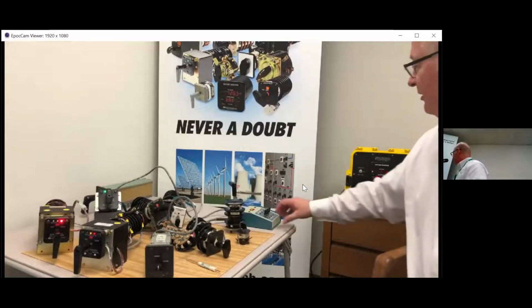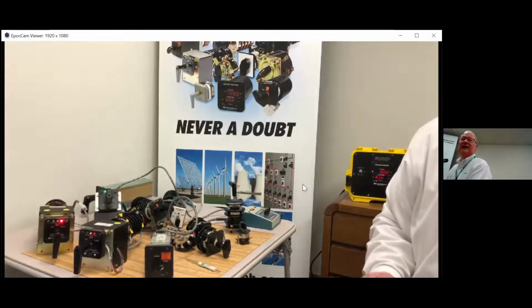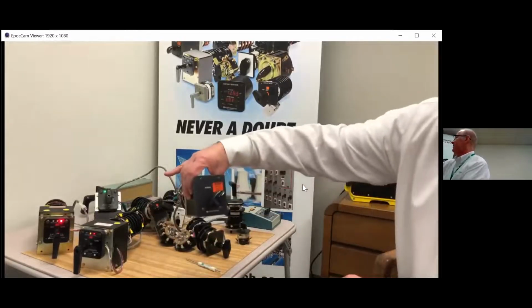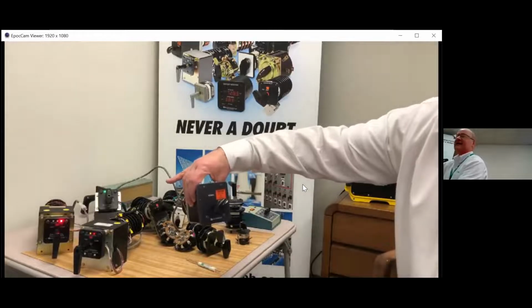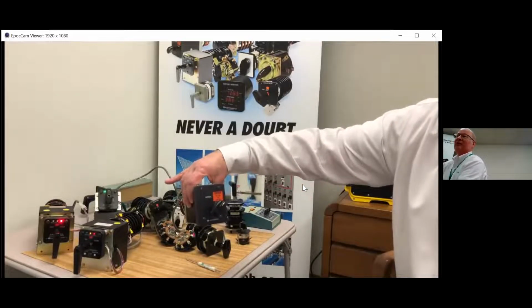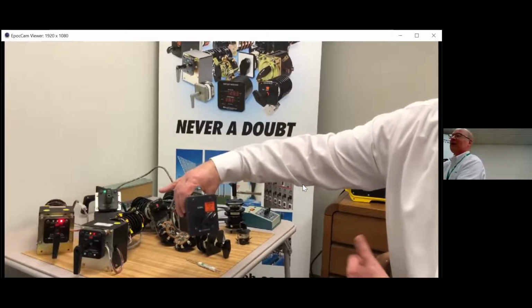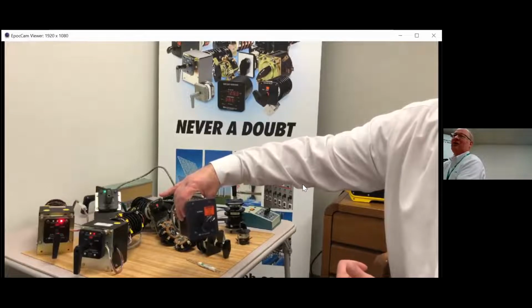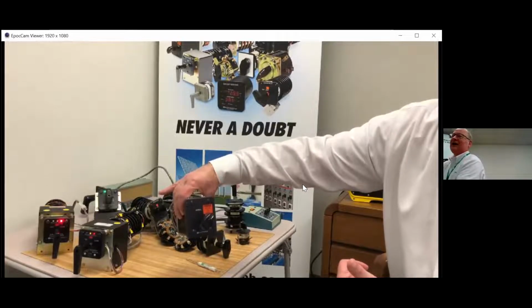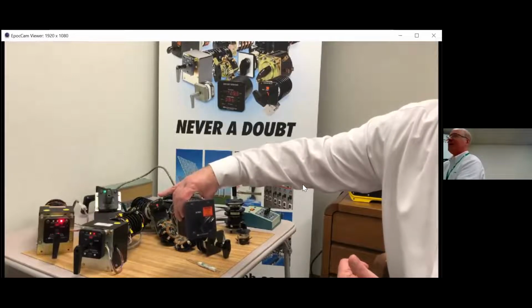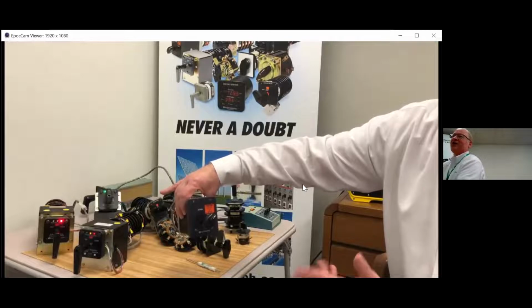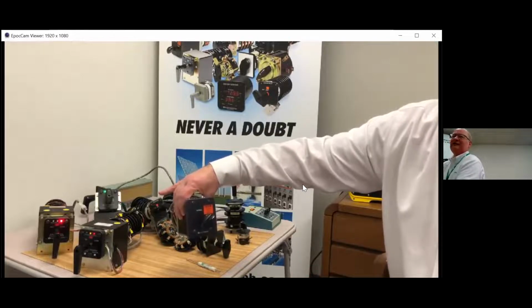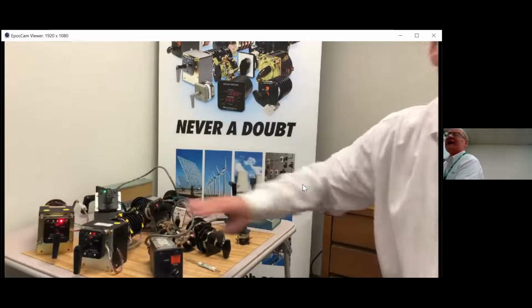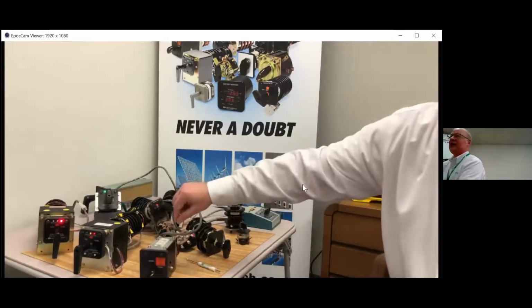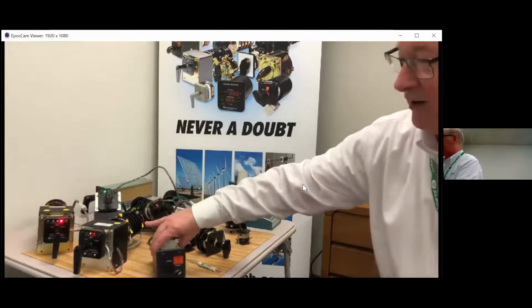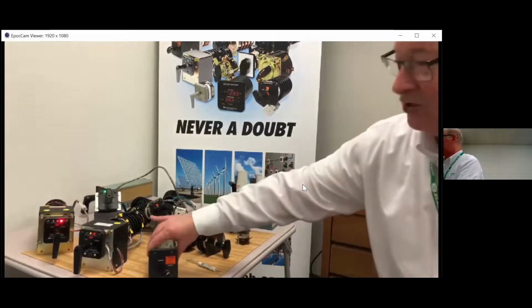And in this particular case, then you can have a SCADA operated tag, and in this case the tag says caution, hotline tag applied. And so when this switch is operated and has that hotline tag applied, you are the first on and last off lock, essentially lockout tag on that maintenance system for that particular breaker. And you can make sure that everybody's got their tags off, their locks removed, before you go ahead and activate this switch. And so it's a latching relay, and it latches in all of those contacts or unlatches all of those contacts that you have wired into the control scheme for that particular application.